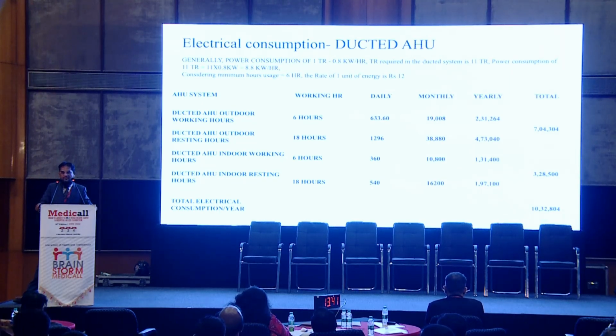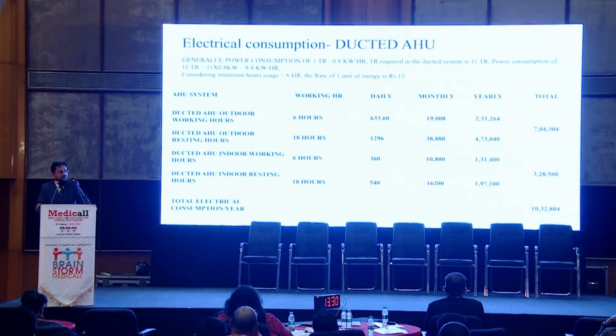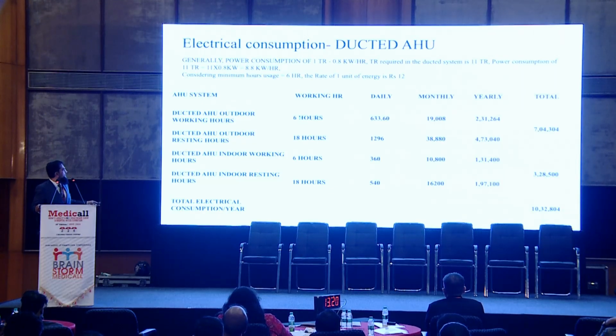If I calculate with all these things, you are going to say almost 50%. No, it's less possible that you can save 50%, but if I calculate 50% efficiency, you are running, so 50% of the electrical expenses you are cutting. Then also, if you do the calculations, 6 hours are the running hours and 18 hours are the non-functioning hours for the outdoor unit and the AHU.